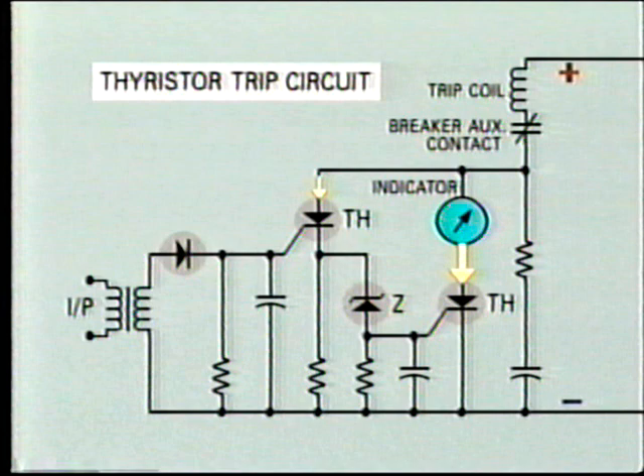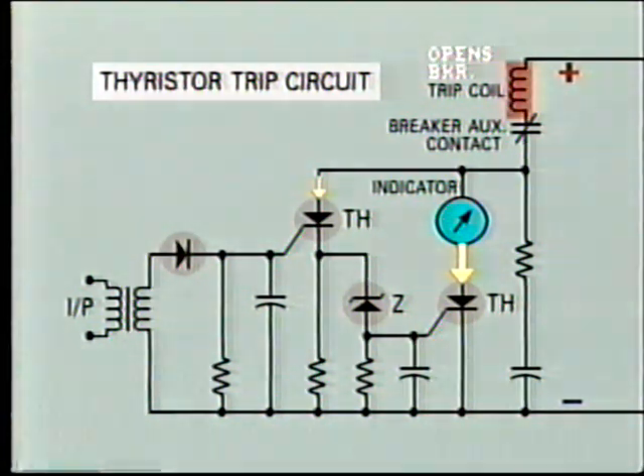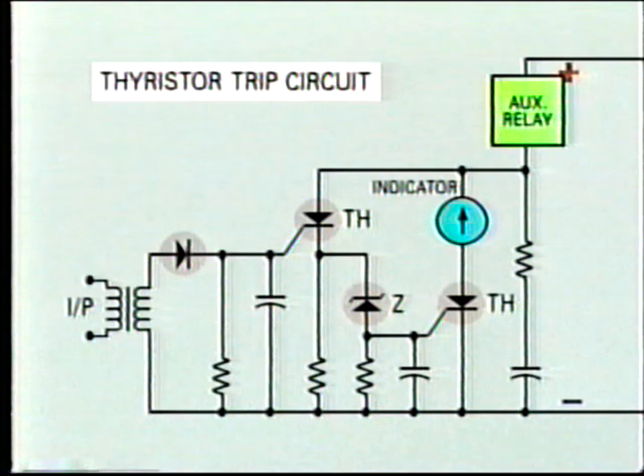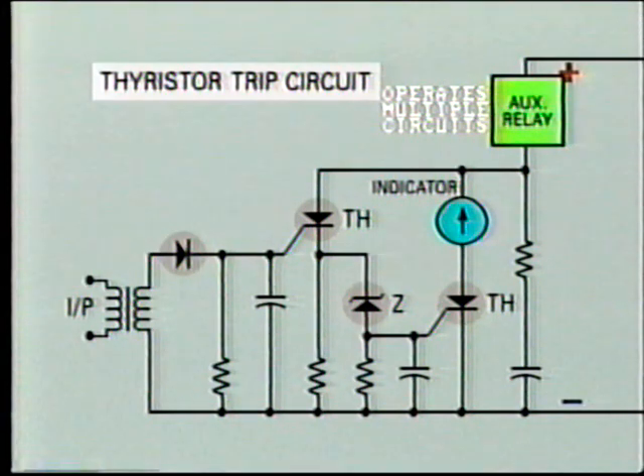Sufficient current now flows through the auxiliary tripping relay to energize the trip circuit and open the circuit breaker. As the circuit breaker opens, the breaker auxiliary contact also opens, and this in turn breaks the circuit through the thyristor, which once turned on does not turn off by gate control. If multi-tripping is required, then the thyristor will operate an auxiliary electromechanical relay, which in turn will close contacts in multiple circuits.